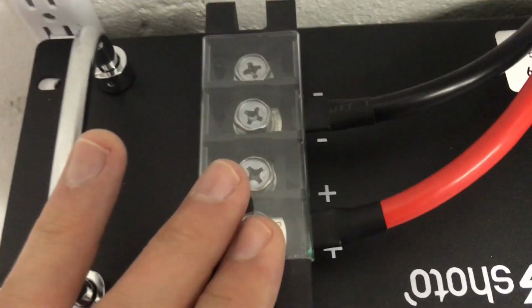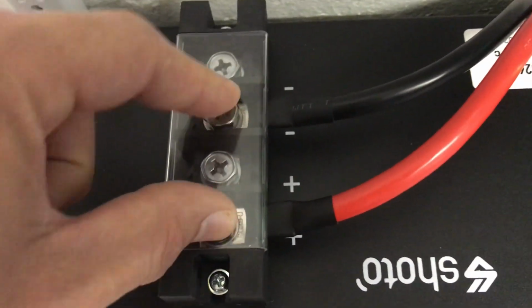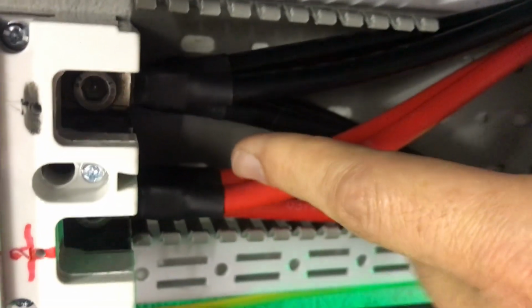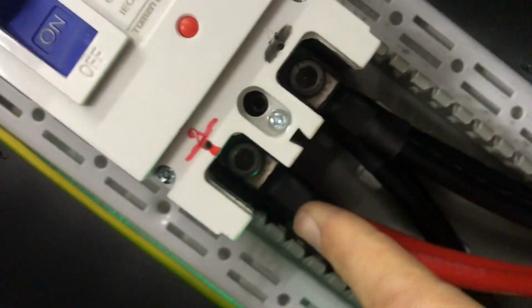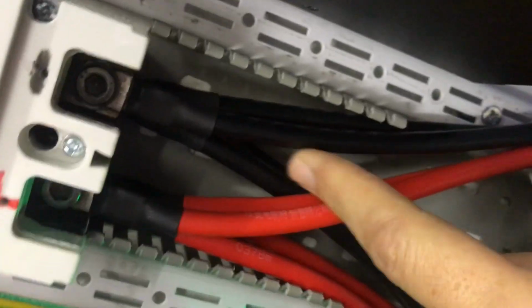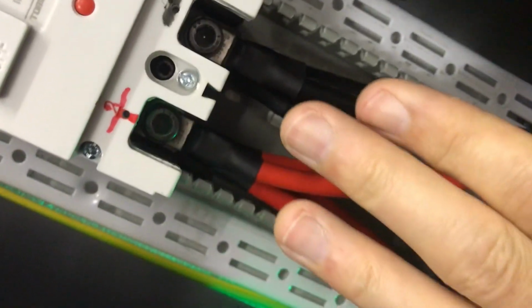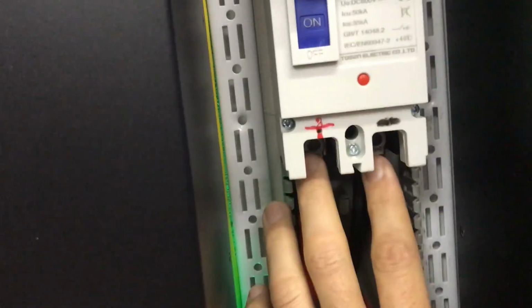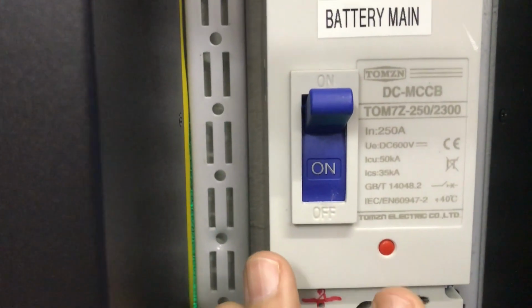And then the two battery terminals are basically just connected over here for every battery. Right, they all go together into what's essentially a bus bar. So there's four battery wires coming onto one bolt over here, and there's another four going to this one bolt over here. So there's purely four batteries connected in parallel to my DC breaker, which can do 250 amps. That's then connected to my two main feeders for the battery to the inverter.